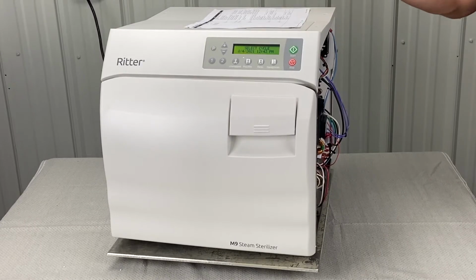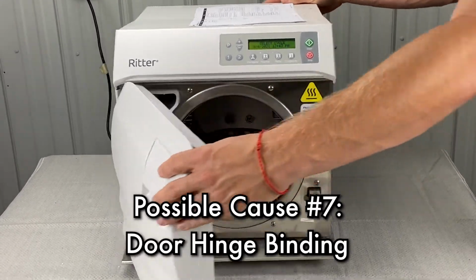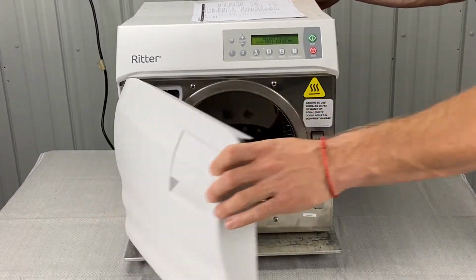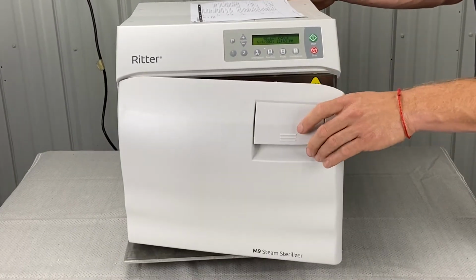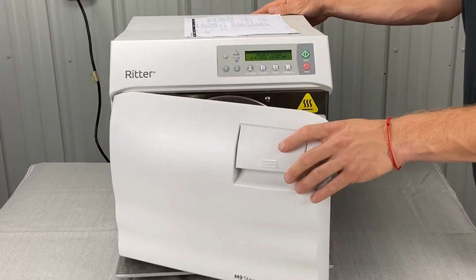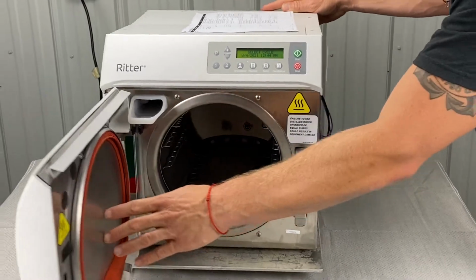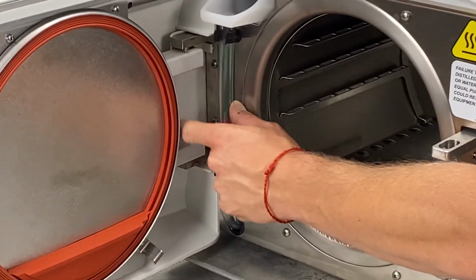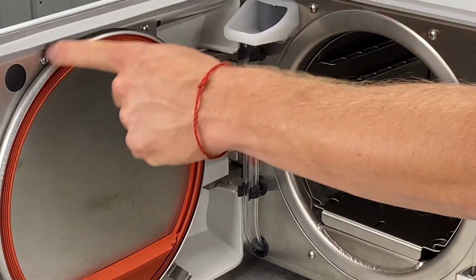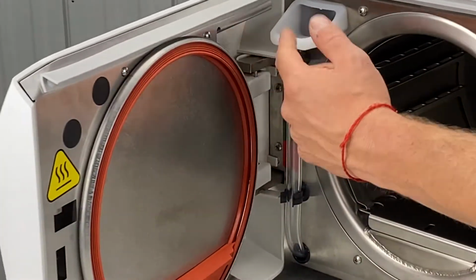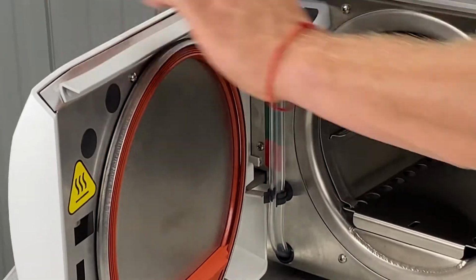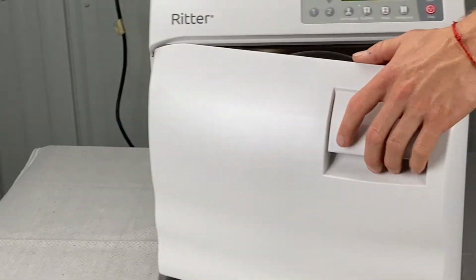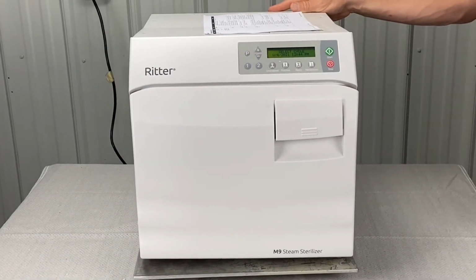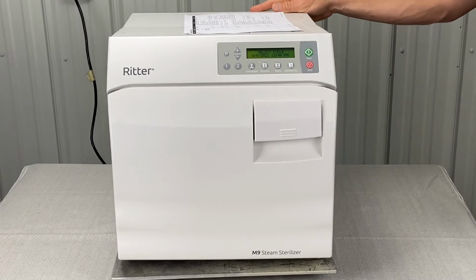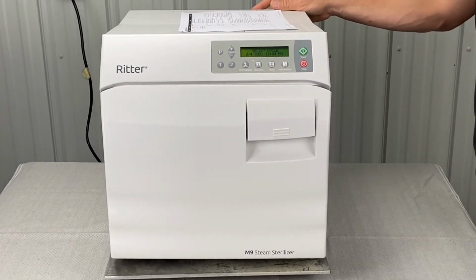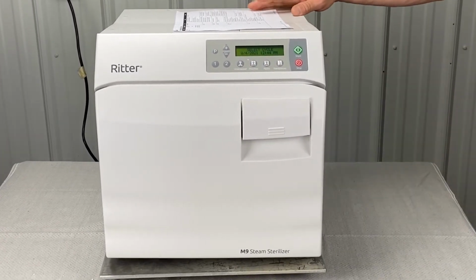So door hinge binding. This should move like this pretty freely. I don't often see the door hinge binding, but it could be because there's a little loose plate in there that may have come loose. It could be one of your studs on the door itself is broken and causing some things like the plastic door hinge to hold up. If you got an older unit, that tends to happen pretty commonly. The steam just breaks them down and they end up cracking. So door hinge, door binding, door motor.